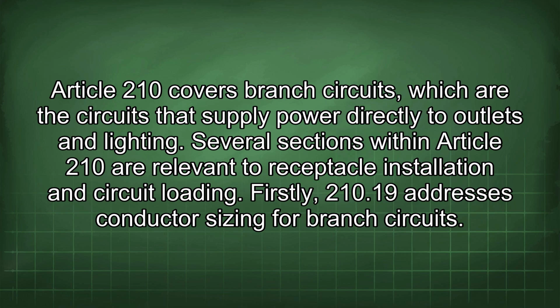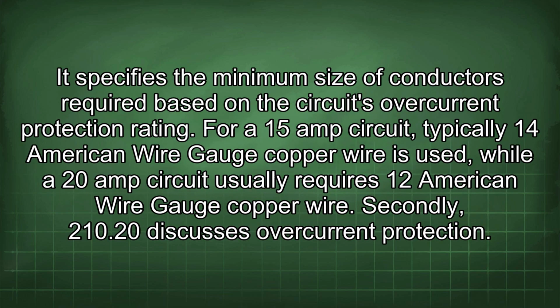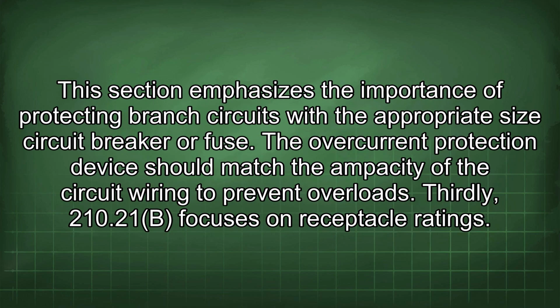Firstly, 210.19 addresses conductor sizing for branch circuits. It specifies the minimum size of conductors required based on the circuit's overcurrent protection rating. For a 15 amp circuit, typically 14 American wire gauge copper wire is used, while a 20 amp circuit usually requires 12 American wire gauge copper wire. Secondly, 210.20 discusses overcurrent protection. This section emphasizes the importance of protecting branch circuits with the appropriate size circuit breaker or fuse. The overcurrent protection device should match the ampacity of the circuit wiring to prevent overloads.